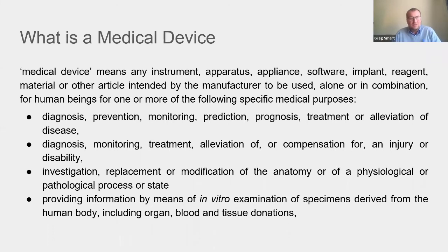But if you are doing any kind of processing, and a very common scenario might be an IoT solution where you've got a physical device connected to an app and the phone is acting as a hub, or where you've developed a standalone app which does some processing of the data that it gathers, perhaps from the onboard sensors or from data entered, all of those things would probably fall into the category of a medical device. So the scope is very broad. It doesn't leave a huge amount of scope for software that has some medical purpose to not be considered a medical device.